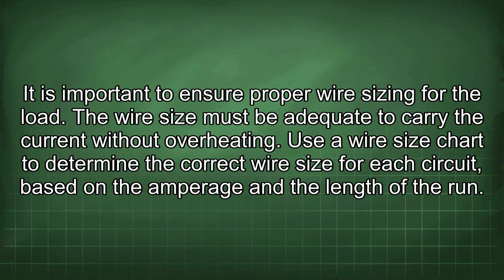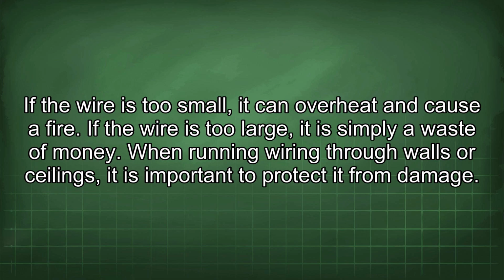It is important to ensure proper wire sizing for the load. The wire size must be adequate to carry the current without overheating. Use a wire size chart to determine the correct wire size for each circuit based on the amperage and the length of the run. If the wire is too small, it can overheat and cause a fire. If the wire is too large, it is simply a waste of money.